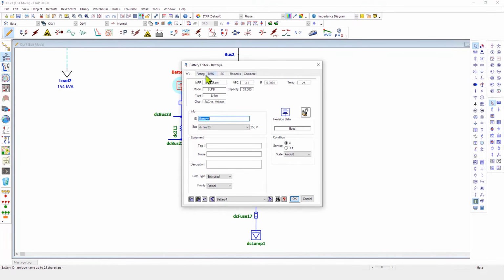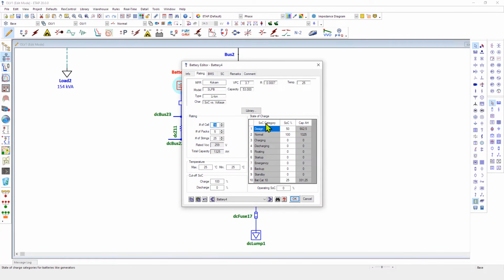You can simply open up the battery editor by double-clicking on the battery element, and once you go to the rating page, you can essentially see a definition of various state of charges. This is similar to the loading and generation category in ETAP for generators as well as loads. Of course, for the battery, we have also defined the number of cells, number of packs, and number of strings. The rated open circuit voltage is essentially nothing but the volts per cell times the number of packs and the number of strings. The total capacity again is the number of strings times the capacity of the battery.